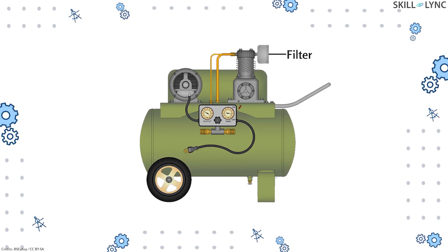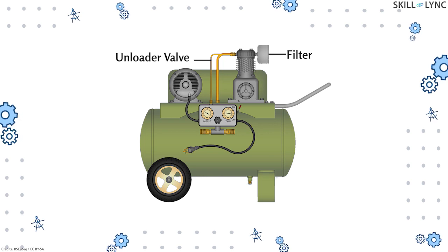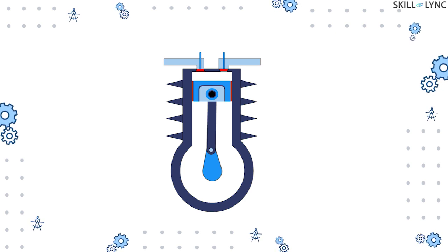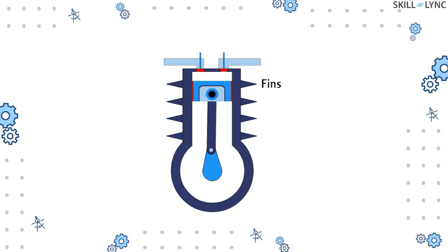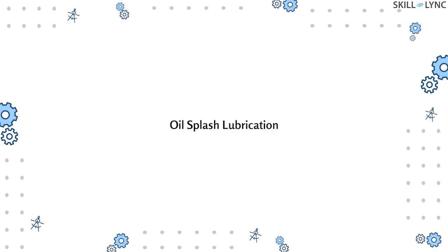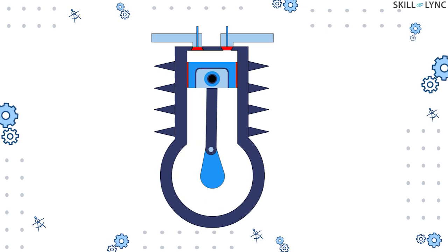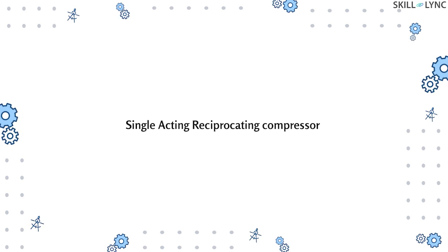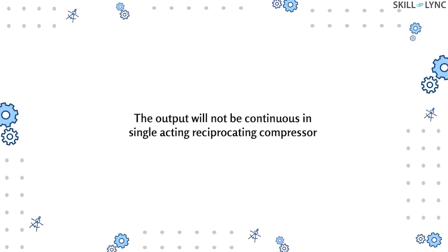Here the air enters the compressor through a filter, and the storage tank is provided with an unloader valve which releases the excess pressure. The compression of air results in high temperature, so to cool down the system, water jackets or fins are provided to the compressor. The lubrication of the piston is done by the oil splash method, and the piston is provided with a seal to avoid oil entry into the chamber.